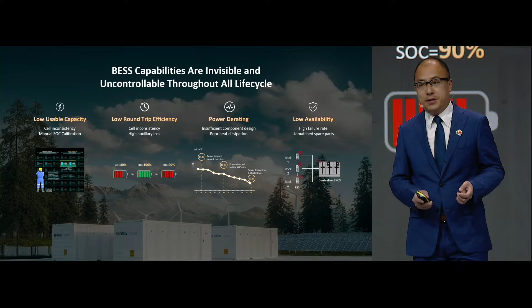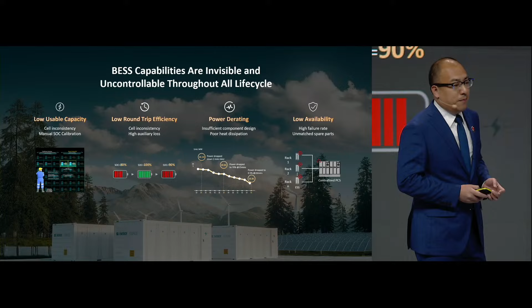In order to secure the return on investment of a BESS project, key performance indicators like usable capacity, round-trip efficiency, power output stability, and availability need to be visible and controllable. However, in actual applications, battery capacity and efficiency usually decrease beyond expectations due to cell mismatch and power output derating because of high temperature. Also, system availability is low due to the centralized design. Therefore, those key parameters need to be visualized and managed in the whole life cycle.